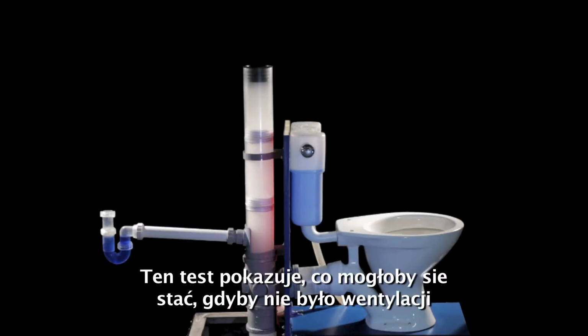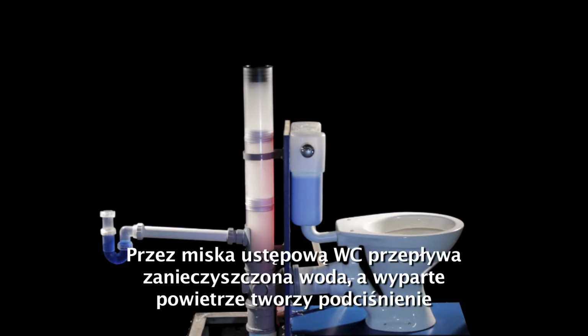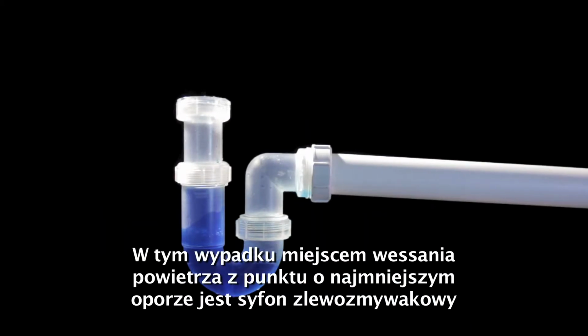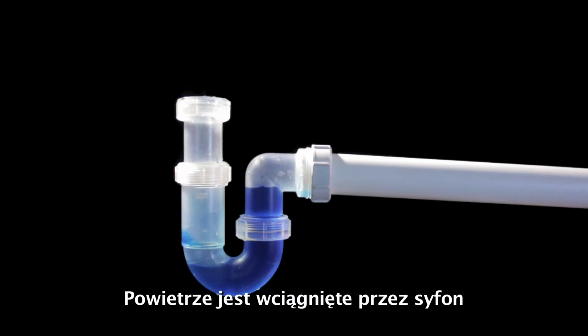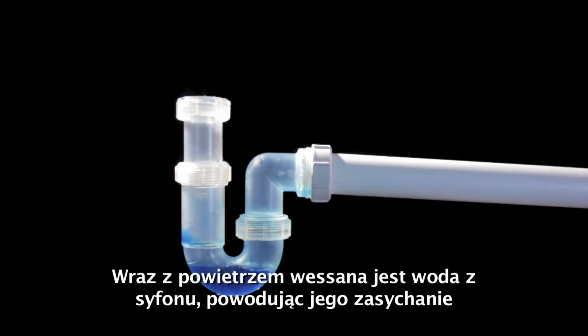This test shows what would happen if there was no ventilation. The WC is discharged and air is displaced, creating negative pressure. Air must be drawn from somewhere. The path of least resistance is the sink trap. Air is pulled in through the trap. This also sucks out water, which drains the seal.